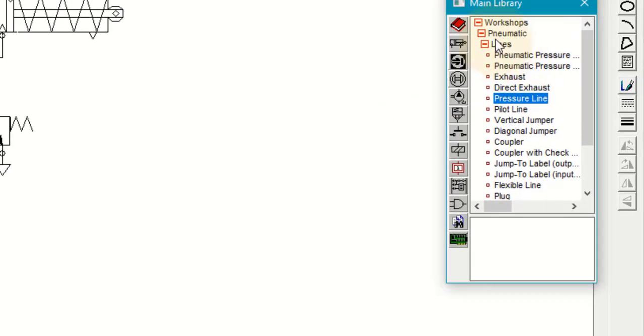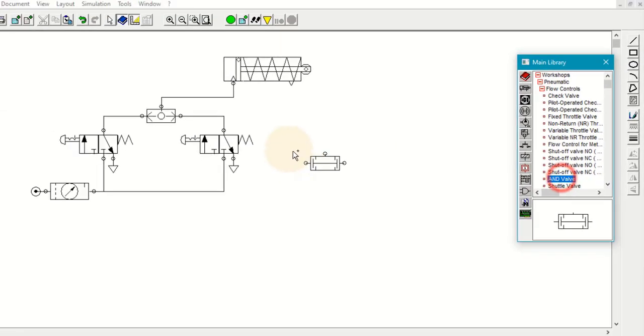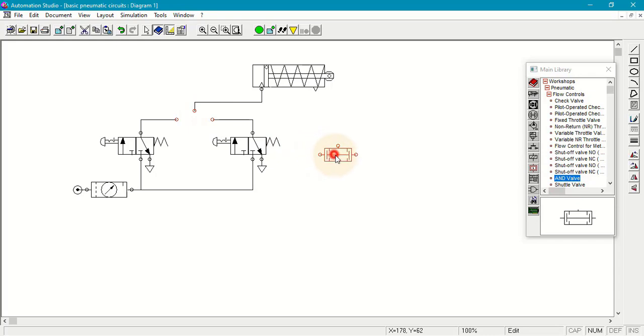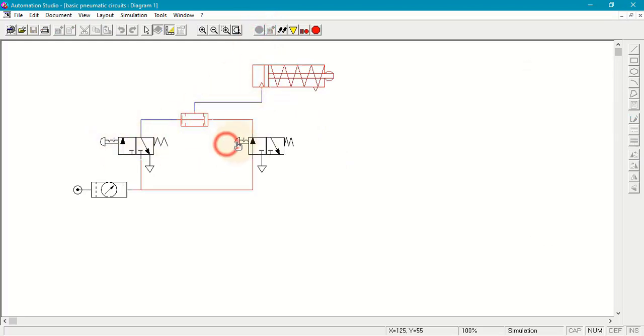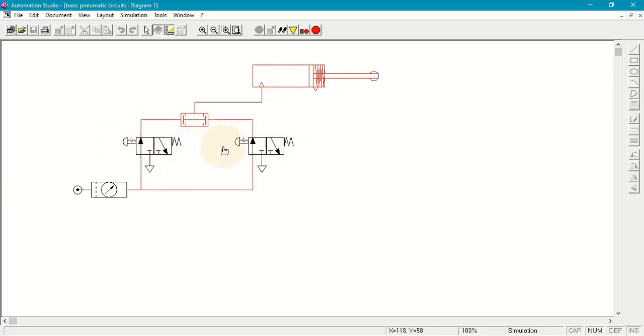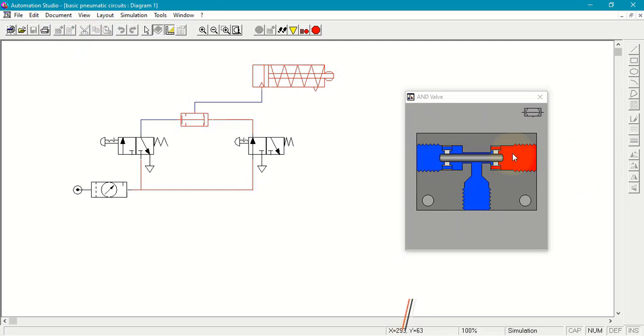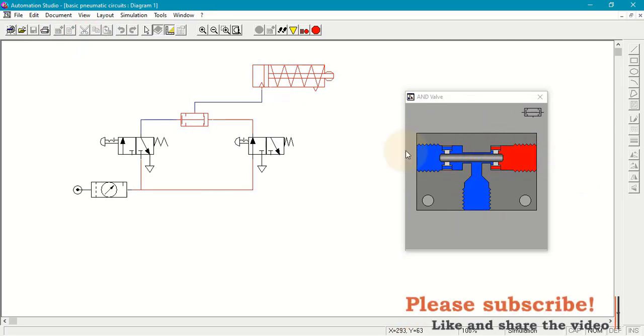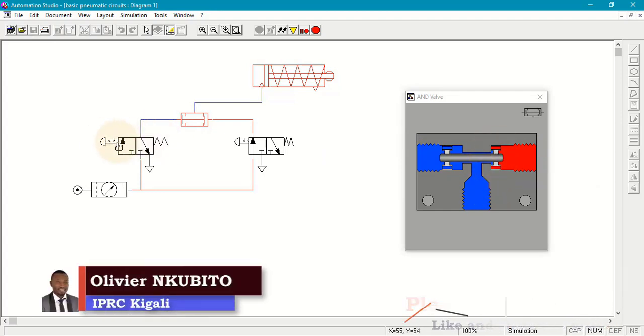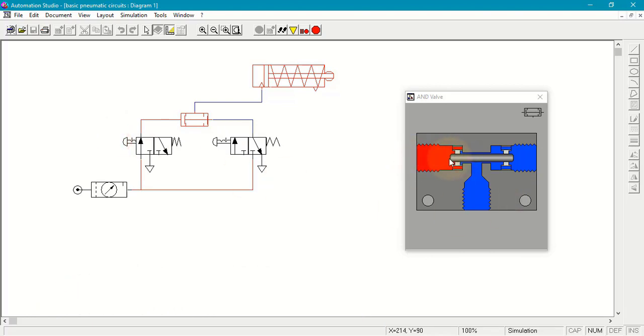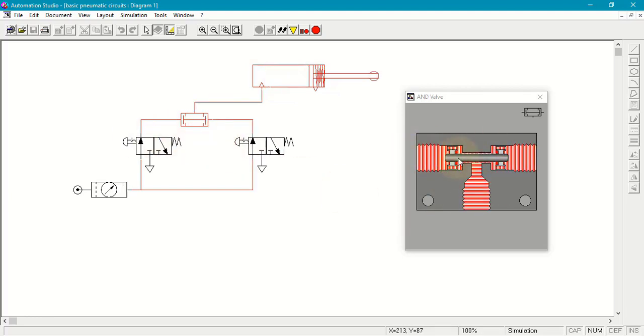Now let's put the AND logic. We go to flow control valves and bring the AND logic valve. At 0, 0 — no extension. At 0, 1 — no extension. At 1, 0 — no extension. But when both DCVs are activated — at 1, 1 — the cylinder extends. Looking inside the AND valve: if only one side is supplied, the pressure pushes the plunger to the opposite side and closes the path. The same happens on the other side. So there is no output. But if both sides are supplied, the plunger stays in the middle and we get the output. That's AND control.